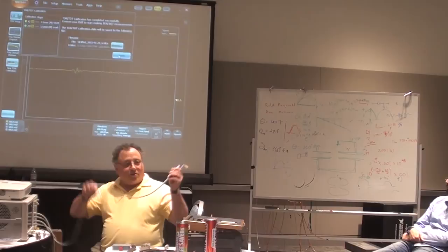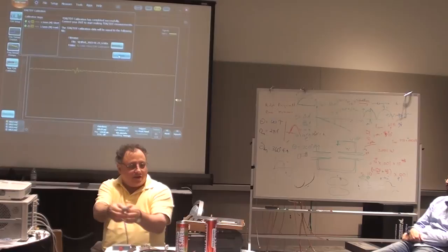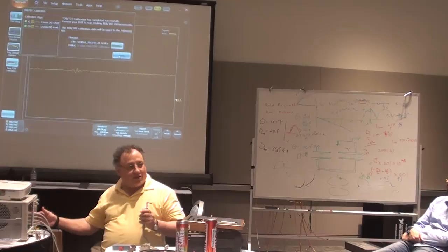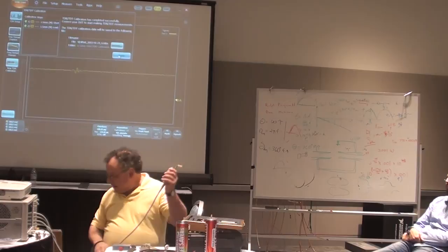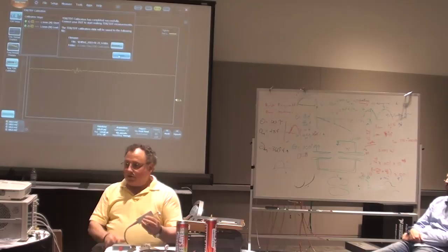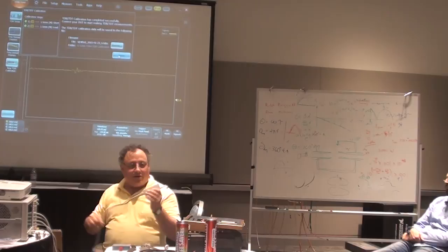And if you read the fine print here. It's going to store the calibration someplace. And you'll be able to define where you're storing this calibration. The thing that's kind of nice though. Is you notice I'm doing all of this. This is all IF low frequency information. I've got this. I can actually bring my test head to the part. The reason why this is so good. In the past they would have to have the connectors on the front panel. You'd have to get your fingers in there to try to torque it around. And you could do a lot of damage to the front panel. Because you have to have a cable on there to go someplace. This is a great idea. They put a one meter cable on it. And this allows you to get where you need to go. It stays put. And as you noticed on your network analyzer or anything. If you did a little of this with the cable. Bad things happen. That doesn't happen here. So this is a very good idea.